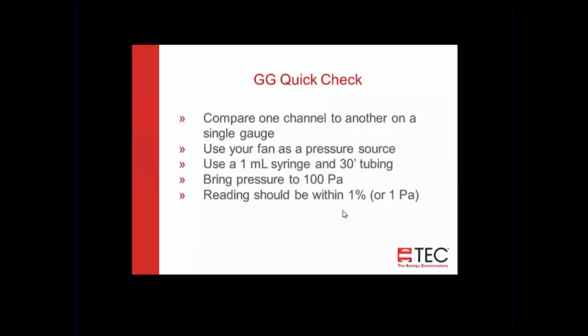And another thing you can do with this setup is compare one channel to another on a single gauge. So with this, we're looking for just large errors in our gauge. So if one of the channels is way off, and we suspect the problem is our gauge, we've done some troubleshooting and we think the problem is the gauge, this is a quick check you can do. If you've got the syringe and 30 feet of tubing, you can use that same procedure. Pull out the plunger till you get to 100 pascals, and they should be within 1 pascal of each other.